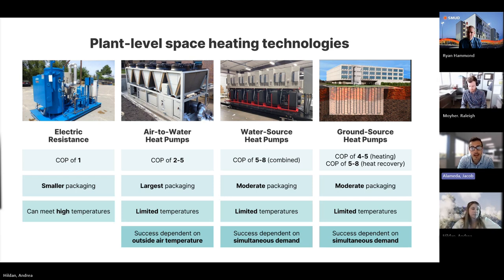So this equipment can get you higher efficiencies than an air source for a couple of reasons. One, it has the opportunity to generate heating water and chilled water simultaneously, which is a plus. Two, it's easier to exchange heat with water than it is air. And three, typically your water source is at a warmer temperature than ambient air temperatures. For example, in Sacramento, instead of having to pull heat out of 40-degree Fahrenheit ambient air, you can pull heat out of a 50-degree chilled water return or something like that.